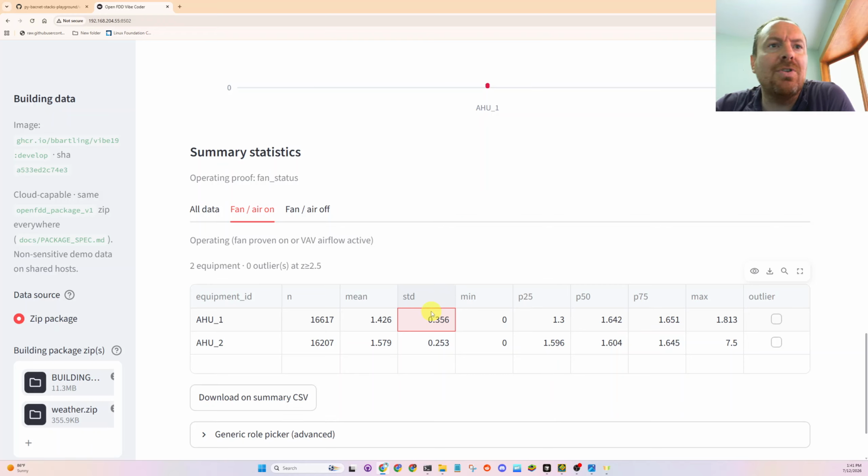And yeah, so there is no duct static pressure reset. There's no temperature resets. There's no resets in the building for energy savings. There's lots of energy savings things here, and maybe a couple VAV boxes that need some looking at that we could see. This is all I have for today, guys.